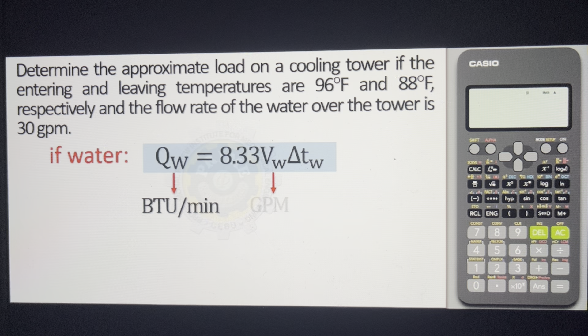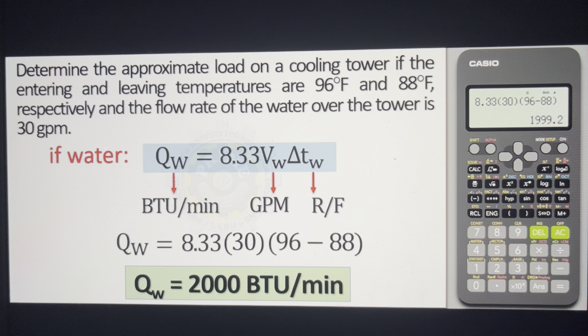So direct substitution: 8.33, times volume flow rate in GPM which is 30. Normally kasi ang cooling tower natin naka-English units, kaya dinerive itong formula na ito. Times the delta T, which is 96 minus 88. So lalabas dyan ang BTU per minute, roughly around 2,000 BTU per minute.